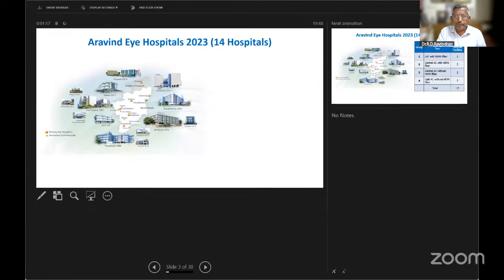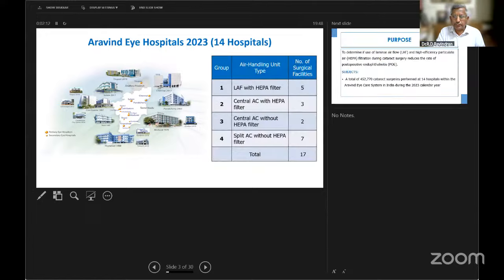Interestingly, our institution started in 1976, and over the last 45-50 years we started hospitals at different points in time. As we start a new hospital we try to comply with statutory norms, so about 5 newer hospitals have laminar airflow with HEPA filter. About 3 built earlier, before 2017, had central air conditioning with HEPA filter. Before that, before 2010, we have 2 locations from 2003 with central air conditioning but without any HEPA filter.